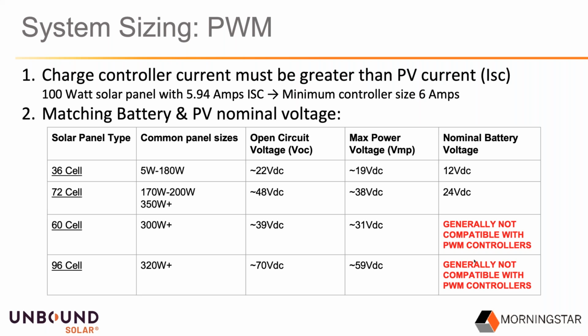This is fairly straightforward. With Morningstar and most controllers, you can even overload them a little bit. You'll want to check the data sheet, of course, and confirm with the manufacturer. For some manufacturers, you may even be able to use a 5 amp charge controller. Honestly, this is a pretty small configuration and there aren't a lot of charge controllers available under 10 amps. So, first step: making sure the charge controller current is greater than the PV current. I think that's pretty intuitive.